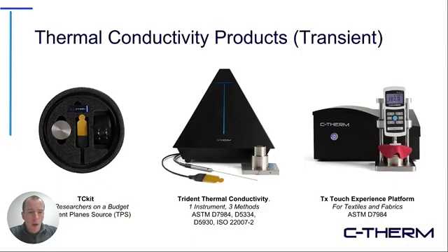Okay, that's it. I wanted to give a quick overview of our product lineup, and the product on the far right is going to be heavily featured in today's presentation. It's the TX Touch Experience platform. It operates an MTPS, Modified Transient Plane Source sensor. And this is what was used in all of the characterization work that Arya has done in support of Susan's project. And we'll be presenting those results shortly.